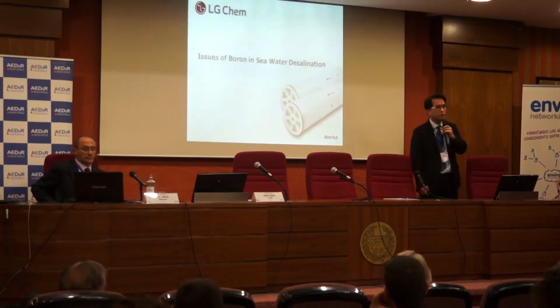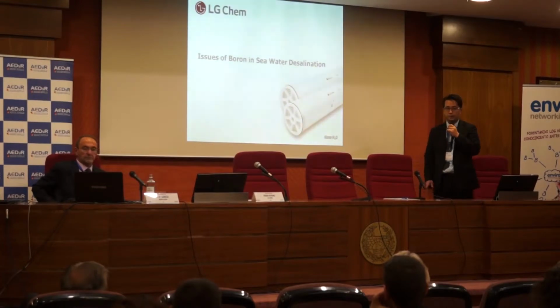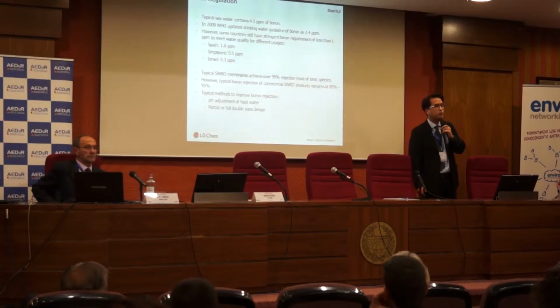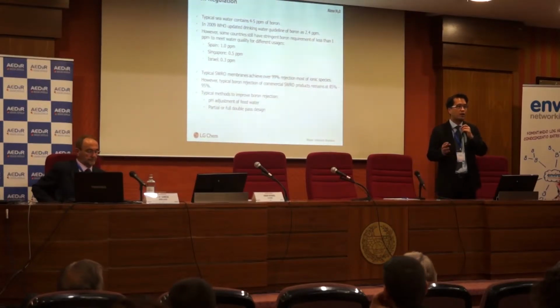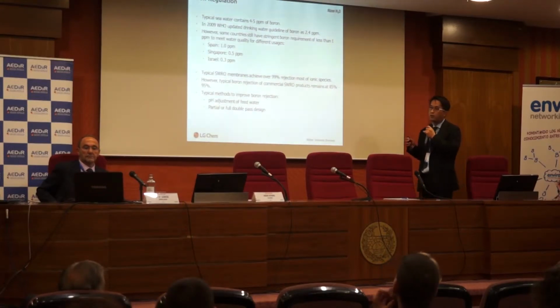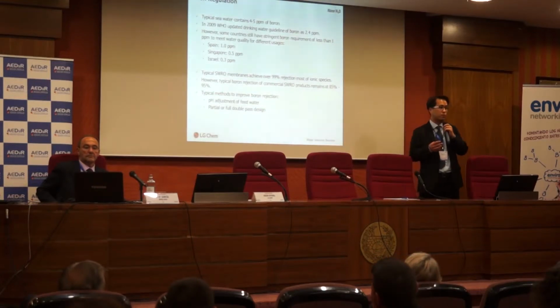So let me talk about the issue of boron rejection in seawater desalination. Before 2009, the boron regulation for drinking water from the WHO guideline was 0.5, and it was basically a limiting factor for seawater desalination plant design. Most of the design was focused on meeting that 0.5 ppm boron regulation. But in 2009, WHO raised the guideline to 2.4 ppm.